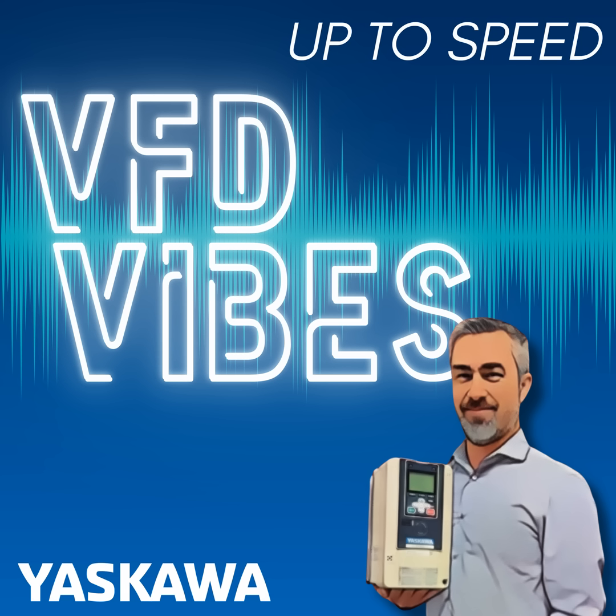While some of these protective devices require that the drive be mounted in an enclosure of a minimum volume. And the reason is that relates to the size of the enclosure used during the short circuit test that a manufacturer performs. And when we do these tests, it's a destructive test. We purposely destroy the drive to see what it can handle with a fuse on its input or with a circuit breaker on its input, etc.